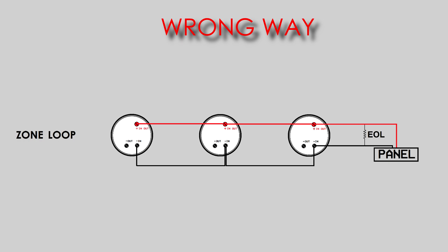In this drawing, you can see that both the positive and negative wires have been blindly looped like a domestic electrical connection and the EOL resistor is connected in the panel itself so that it does not show that the zone is open. I have observed this a lot and this totally defeats the fail safe purpose. So please don't make such stupid connections.